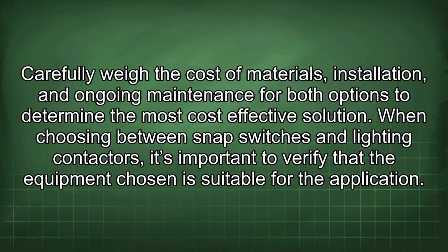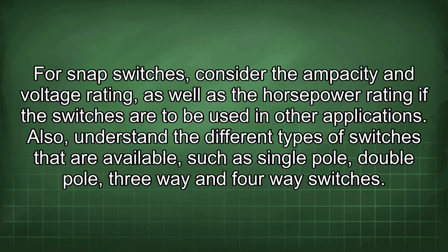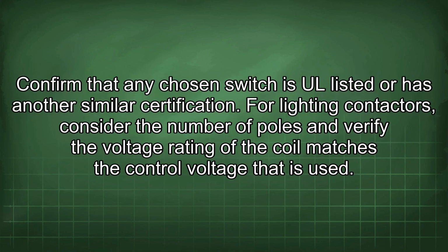When choosing between snap switches and lighting contactors, it's important to verify that the equipment chosen is suitable for the application. For snap switches, consider the ampacity and voltage rating, as well as the horsepower rating if the switches are to be used in other applications. Also, understand the different types of switches that are available, such as single-pole, double-pole, three-way and four-way switches. Confirm that any chosen switch is UL listed or has another similar certification.